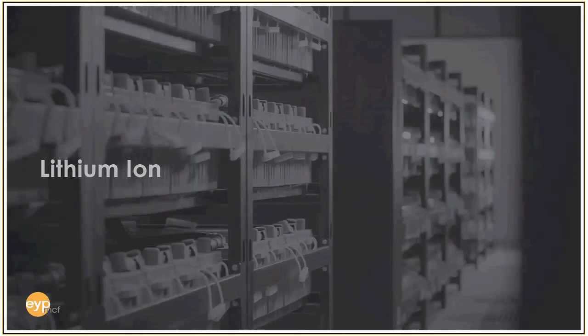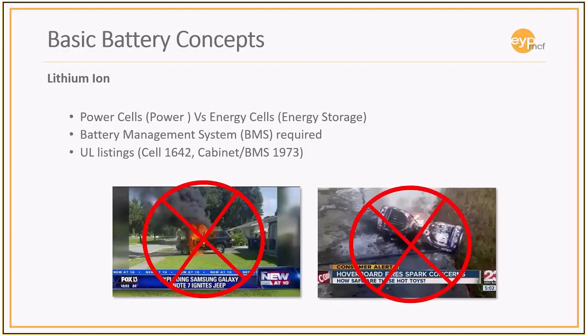We'll talk a little bit about lithium-ion now. Everybody has seen or heard about cell phone battery explosions, but we need to understand that a lithium-ion cell phone battery is not the same thing as the batteries used in our UPS system. You have power cells and energy cells, and we're dealing more with energy cells in a UPS environment. Each of these batteries has its own battery monitoring system built in so that it regulates charging and discharging and doesn't allow it to exceed the design criteria, which is supposed to eliminate the issue with these battery cells catching on fire.